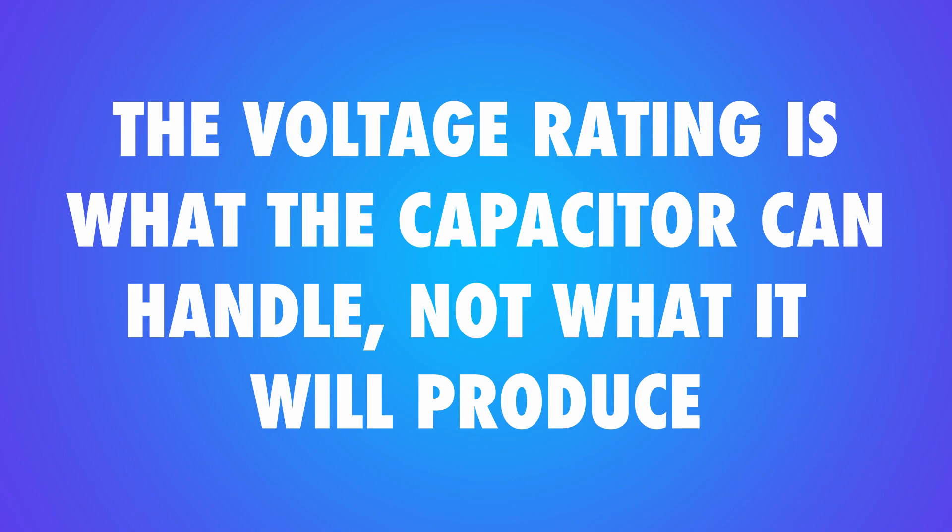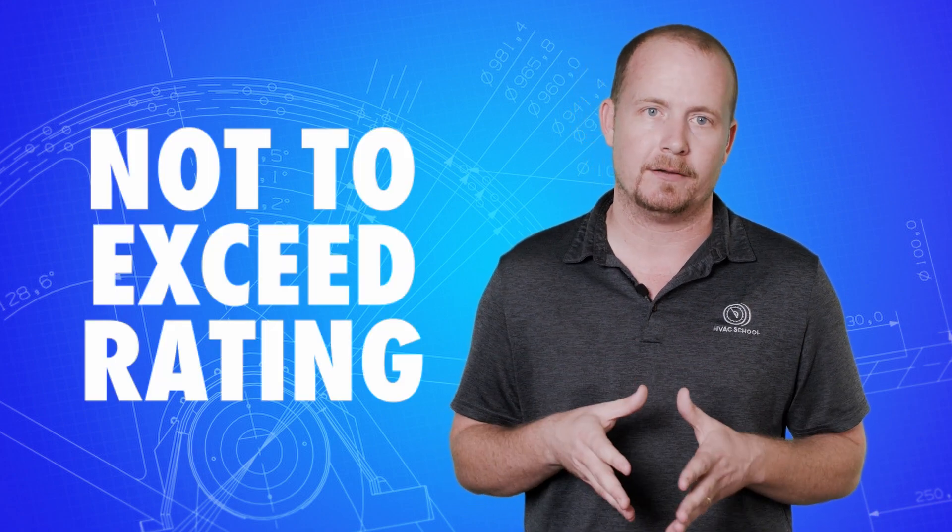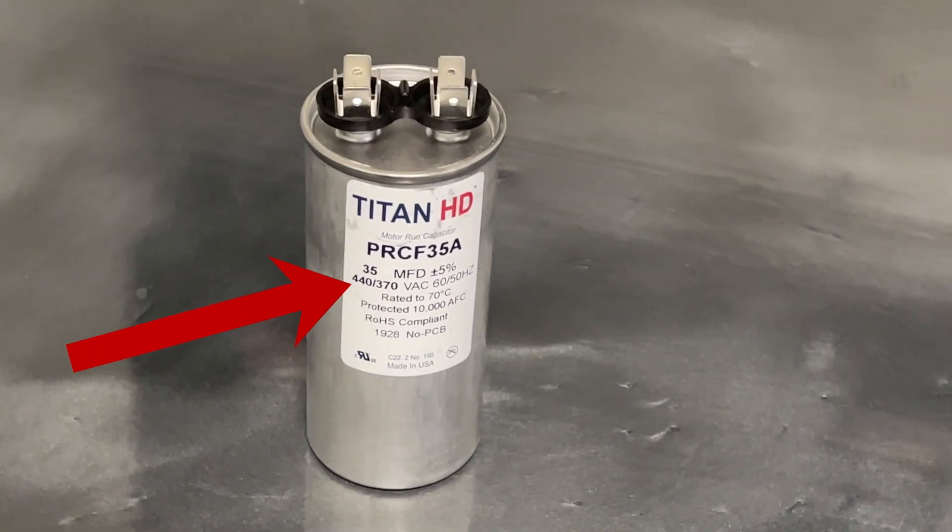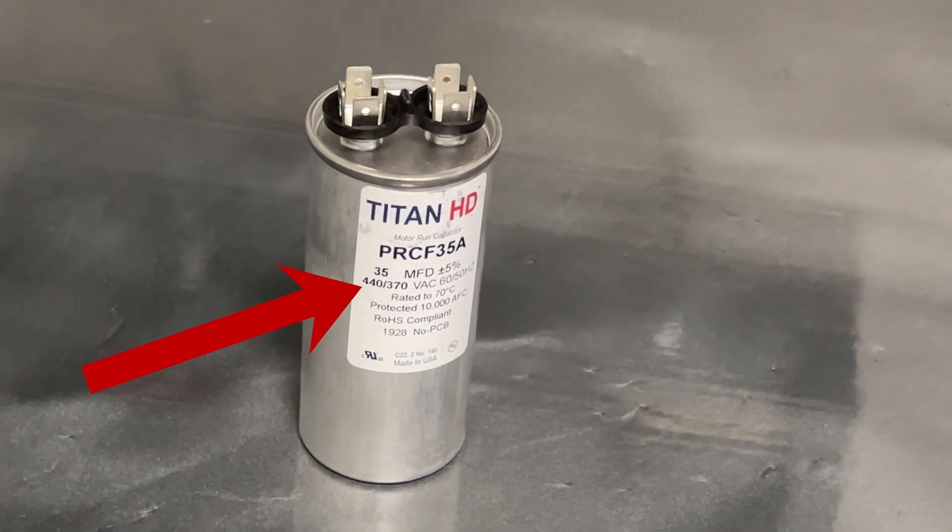The voltage rating is what the capacitor can handle, not what it will produce. Many techs think they must replace a 370 volt capacitor with another 370 volt capacitor. The voltage rating displays the not to exceed rating, which means you can replace a 370 volt with a 440 volt, but you cannot replace a 440 volt with a 370. This misconception is so common that many capacitor manufacturers begin stamping 440 volt capacitors with 370 slash 440 just to eliminate confusion.